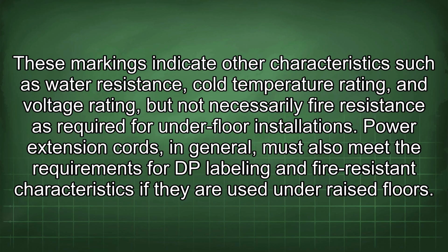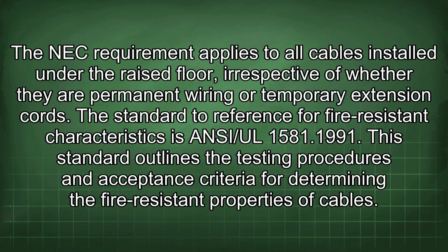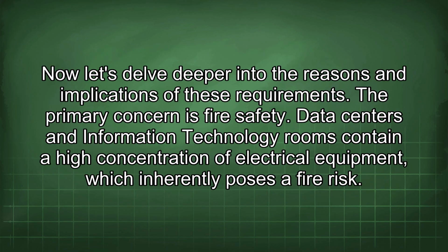Power extension cords, in general, must also meet the requirements for DP labeling and fire-resistant characteristics if they are used under raised floors. The NEC requirement applies to all cables installed under the raised floor, irrespective of whether they are permanent wiring or temporary extension cords. The standard to reference for fire-resistant characteristics is ANSI/UL 1581.1991. This standard outlines the testing procedures and acceptance criteria for determining the fire-resistant properties of cables. Now let's delve deeper into the reasons and implications of these requirements.